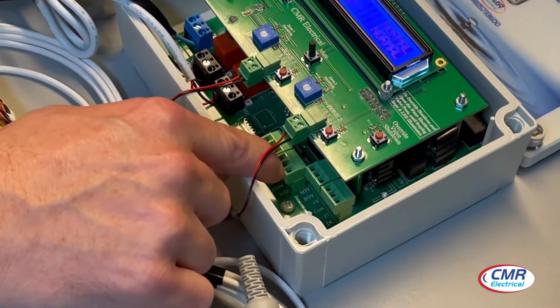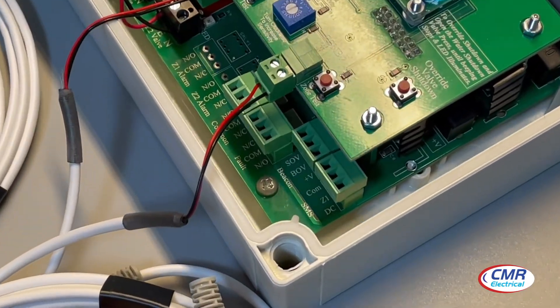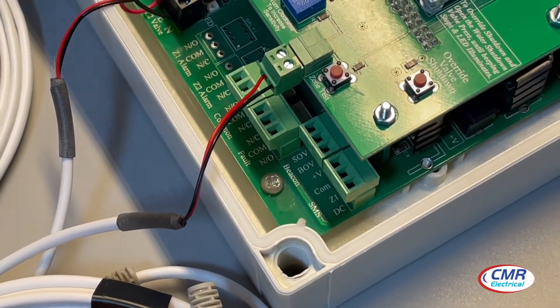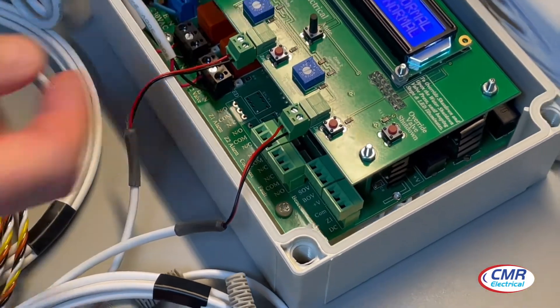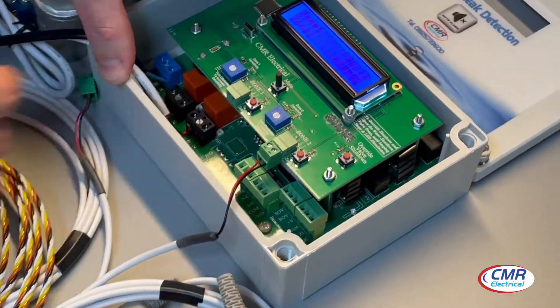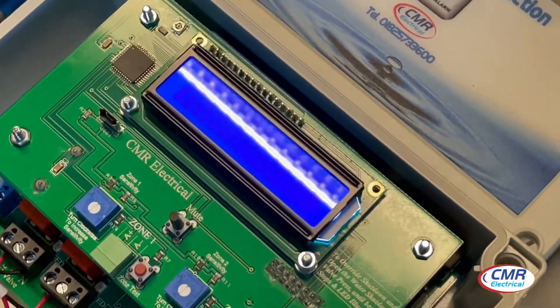Next to that one, you have the fault volt-free contact. That is for when the cable gets damaged. I'll illustrate it by pulling out the terminal in that zone. You can see it says zone 1 fault.